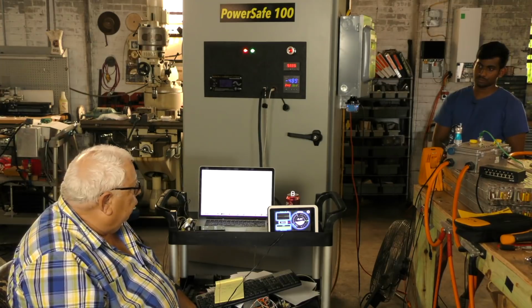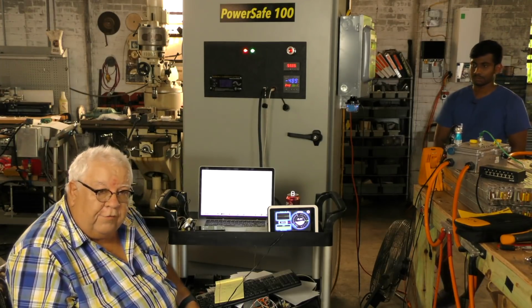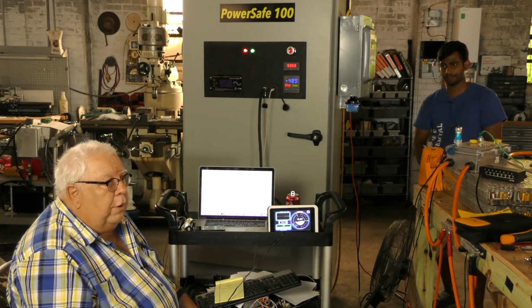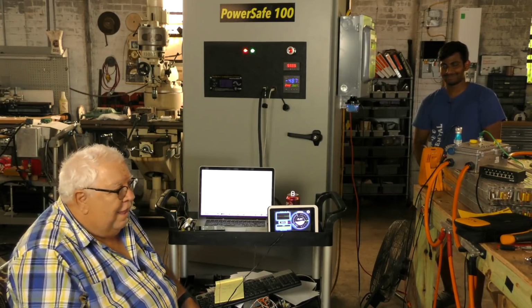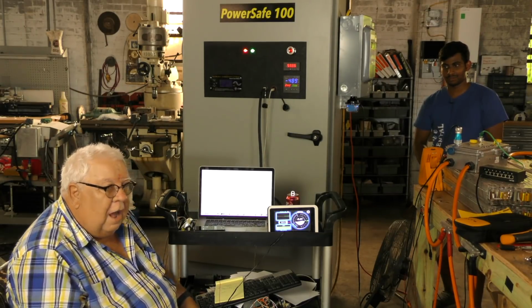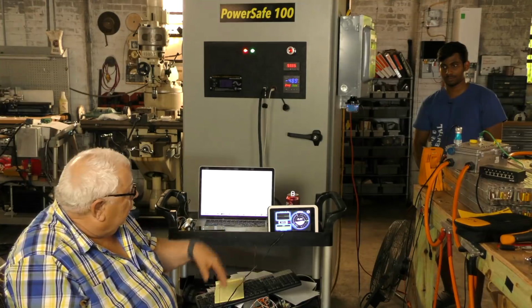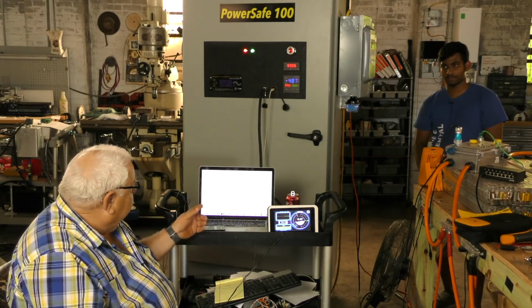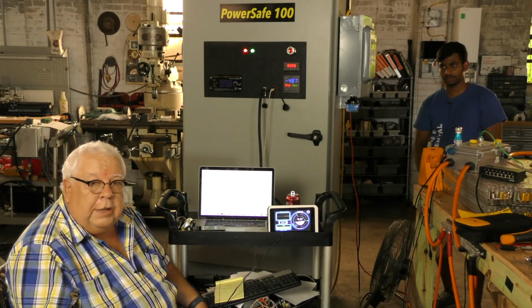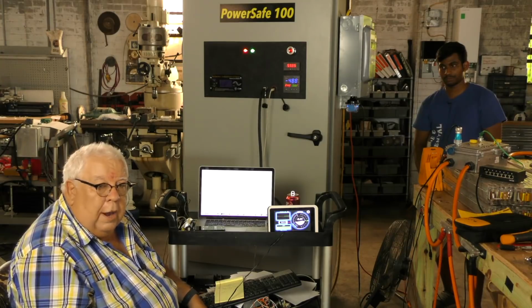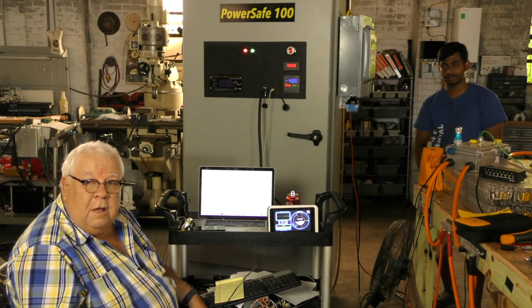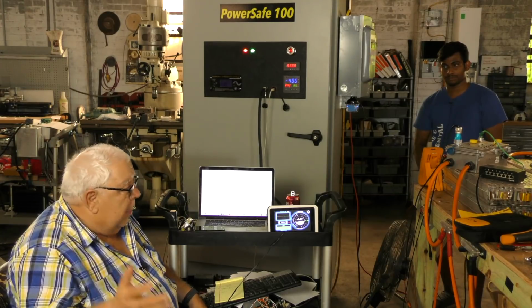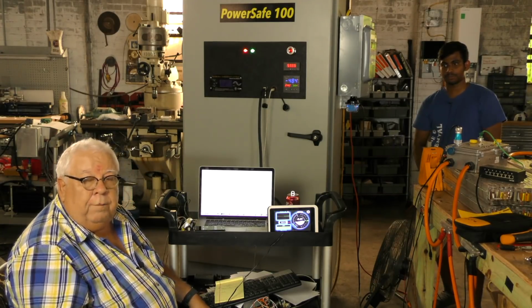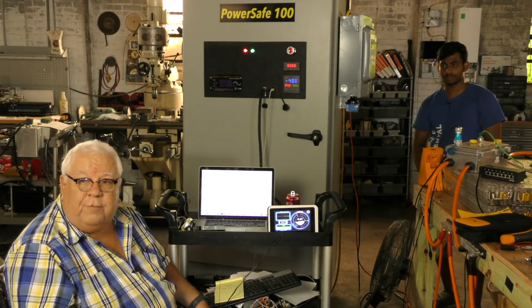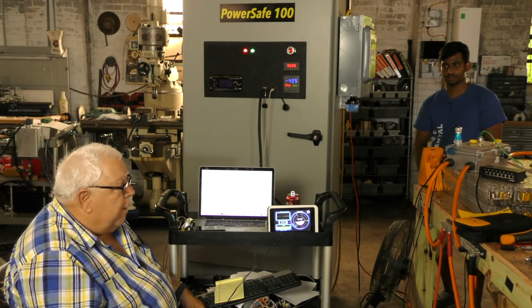It also shows me - and we know that this would be so, but we never actually tested it - that by having a contactor in our solar input box that we can control with charge enable, we can charge those batteries right up to our cutoff voltage, at which point we disengage that contactor and that whole system goes down and will no longer produce power and will not overcharge our batteries.